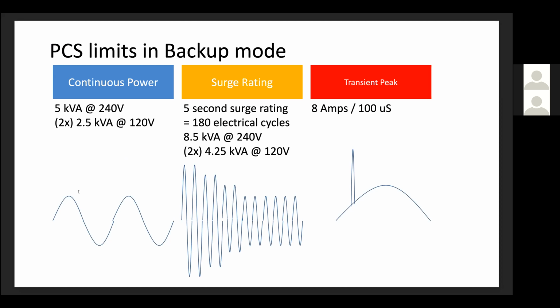The continuous power for a purely resistive load, whether it's a toaster, oven, or whatever, is limited to 5 kVA at 240 volts, or 20.8 amps on either leg of the load circuit. It has a surge rating, a 5-second maximum surge, of up to 8.5 kVA, and 30 minutes up to 6 kVA. And that is split between the two legs. It has the ability to withstand a transient peak of 8 amps for 100 microseconds.